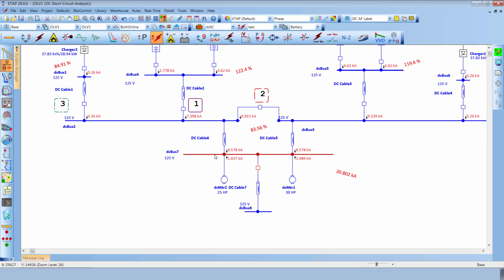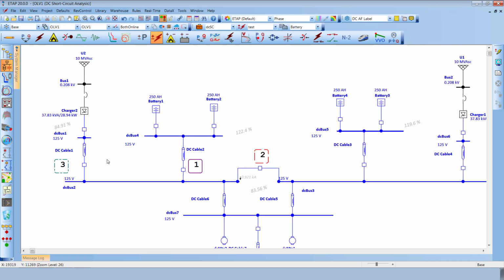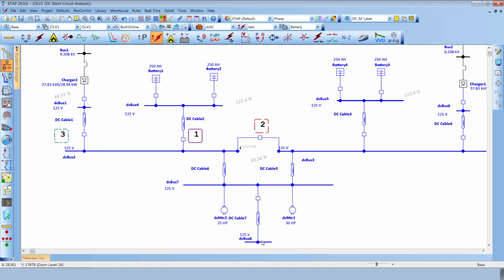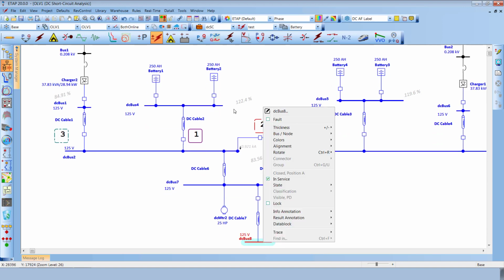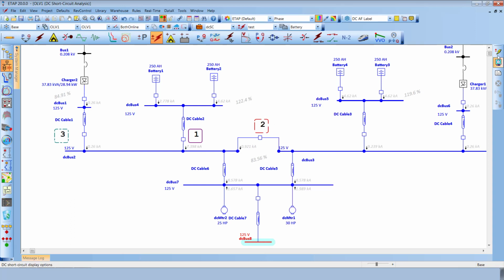Further moving downstream, it reaches a point where it exceeds the V operating max of the charger, which in turn shuts off the charger contribution for the following faulted location. And as you can see, for the given short circuit terminal voltage, which is actually greater than the VOP max, there is no more short circuit current injected to the system.